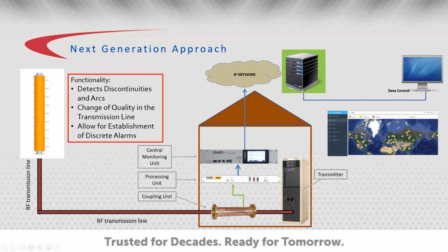The system consists of a coupling unit, which is right here, the transmission line, which then is connected to a processing unit. And that processing unit is connected to the central monitoring unit, which is where you interact with the unit itself. The coupling unit is manufactured to the same size transmission line, and it is installed post-filter and post any waveguide. The signal cannot propagate through waveguide. And it's usually installed before the gas barrier because it's not pressurized.